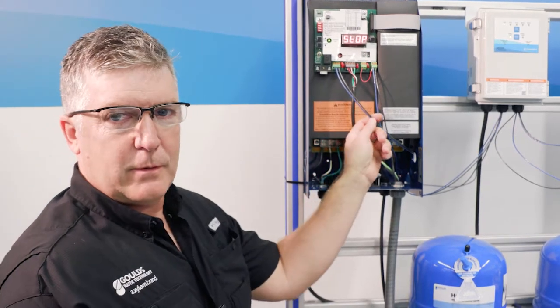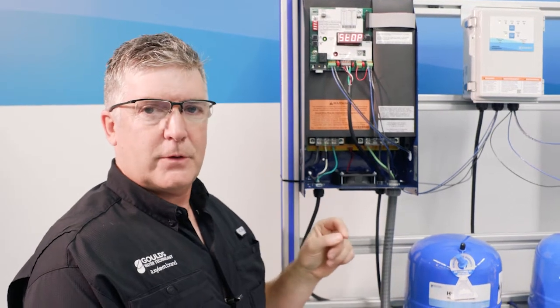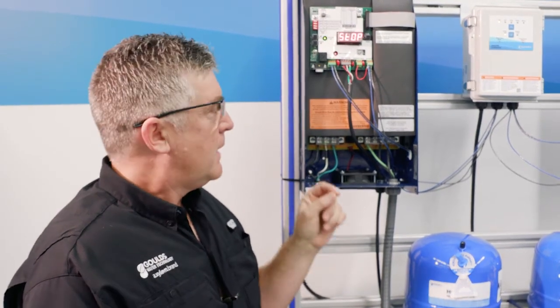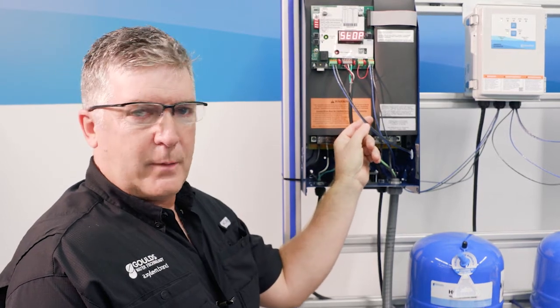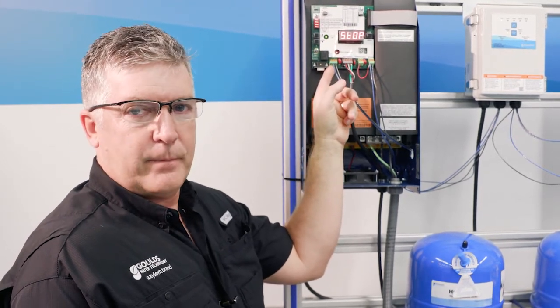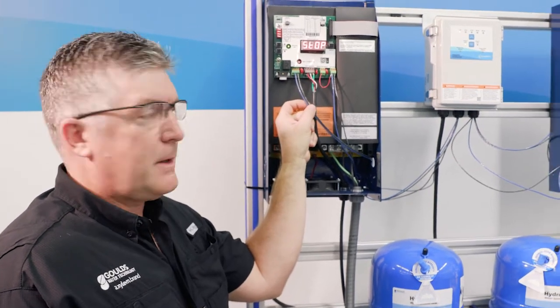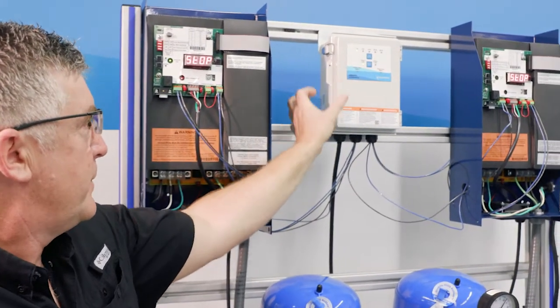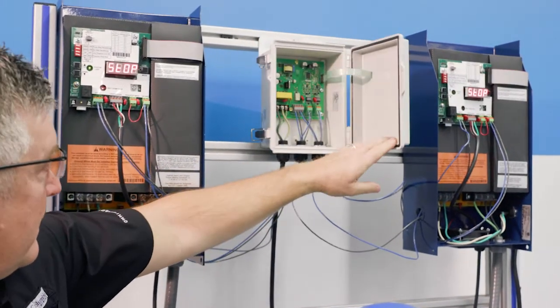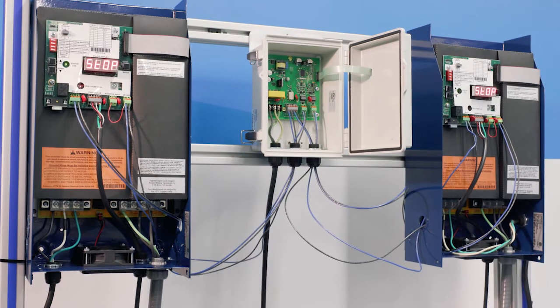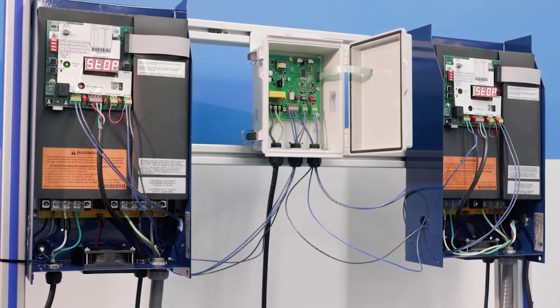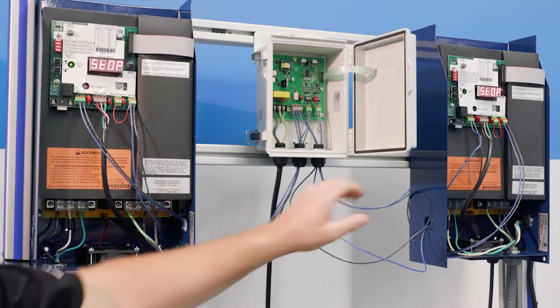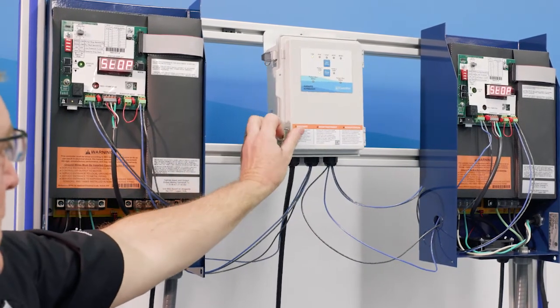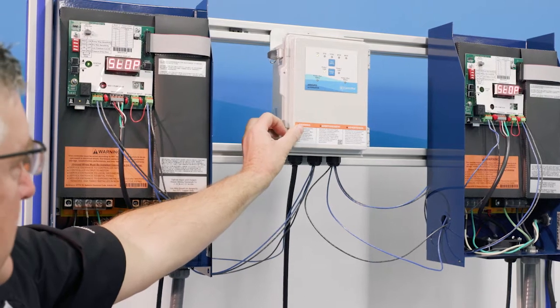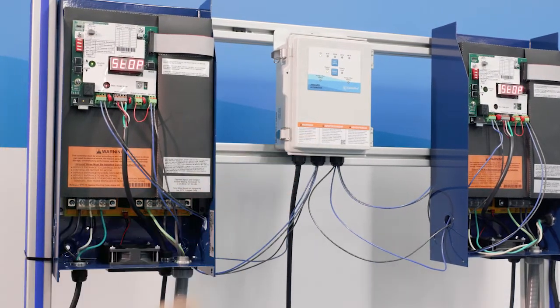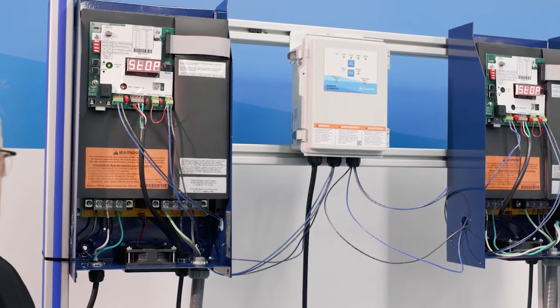Okay, so we talked about the wiring for lead lag alternation based on runtime. And we know we're wired for runtime here because it's going to the relay. If we're not wired to the relay and we've got our terminals jumped in here, these two terminals, then we're wired for lead lag alternation based on elapsed time. All right, so now that we've got our wiring down, which is in the manual, there's a couple things that we need to do to set it up.